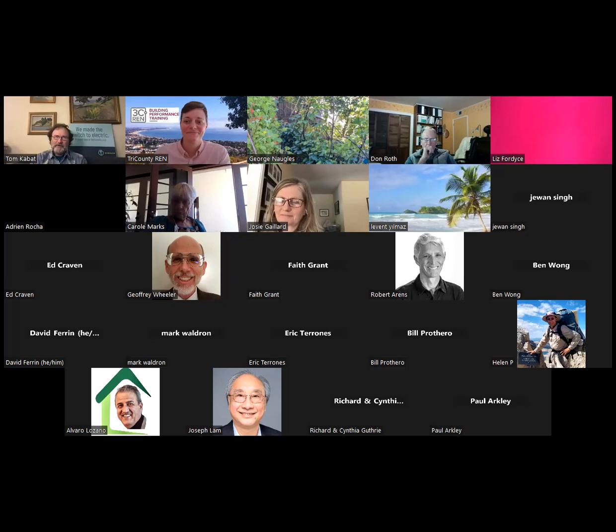Josie and I are part of a group working on a number of areas to make electrification easier. One subcommittee is working on code reforms, trying to produce the empirical data needed for code committees to consider simplifying the process and allowing more electrification on existing circuits. The code doesn't change very often, so it's quite old—that 3 watts per square foot was set when refrigerators, TVs, and everything else used a lot more power. Tom is actually doing work recommending a lower factor, maybe 2 watts per square foot. But those code changes take years to prepare and years to get adopted, so it's not happening anytime soon. For now, you have to use the 3 watts per square foot, unfortunately.